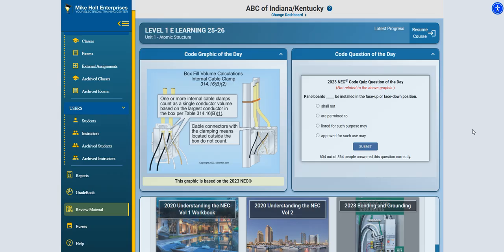I put a device in that box. I'm going to put a double volume on that device, because that is what the code states, that you would use a double volume of whatever the largest conductor is in that box. So now I'm at 12, that's 13, 14, 15, 16. I'm at a total of 16 cubic inches for that box. I'm not really sure off the top of my head what the cubic inch capacity is of that particular cut-in box, but I would say, for example, a standard one gang plastic nail-on is oftentimes around 22.5 cubic inches. So at 16, we're certainly well within the confines of what that box is capable of.